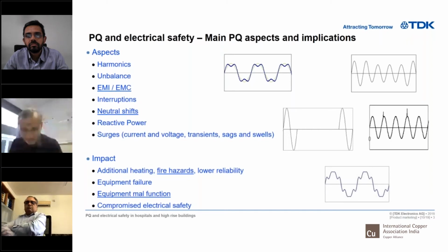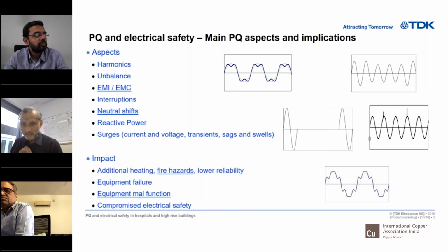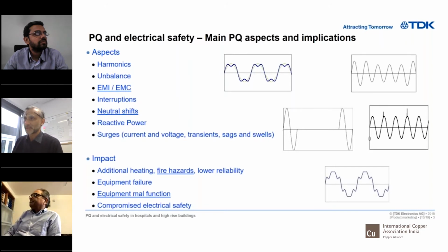In one hospital they had to improve power quality not because of kVAh billing or a penalty or tariff benefit, but because sensitive healthcare equipment was tripping due to harmonics. You're talking about a human life—let's say you're in the CCU, the monitoring equipment malfunctions because of power quality, then a lot more is at stake than the energy bill, and of course, compromised electrical safety.